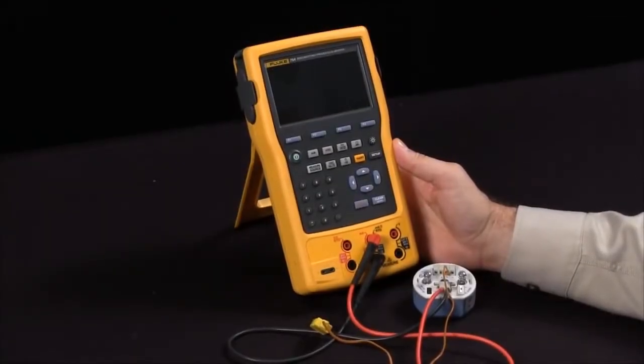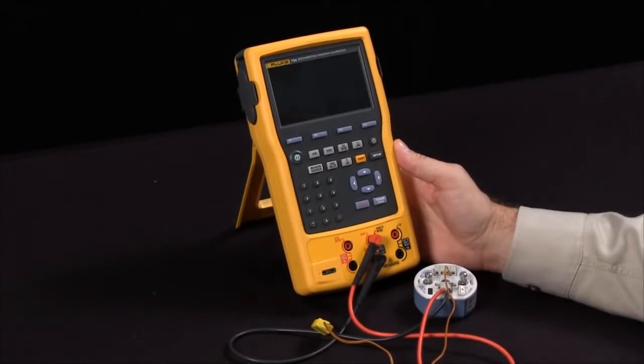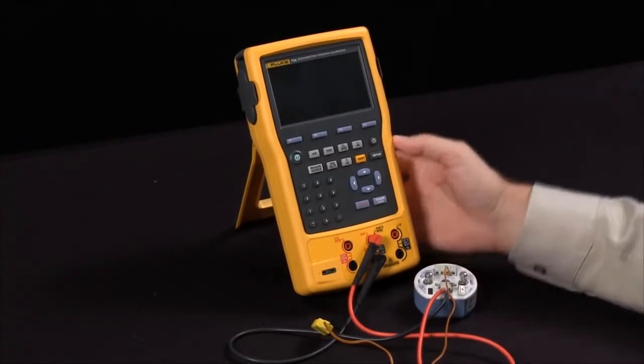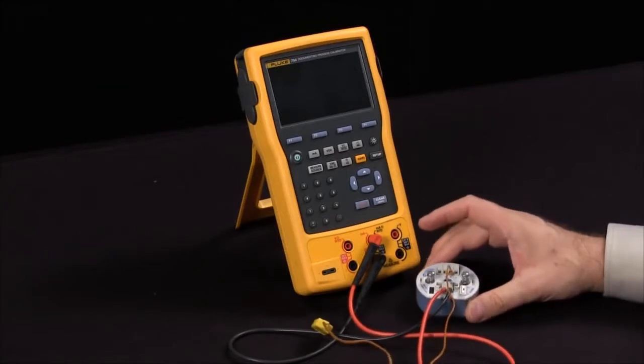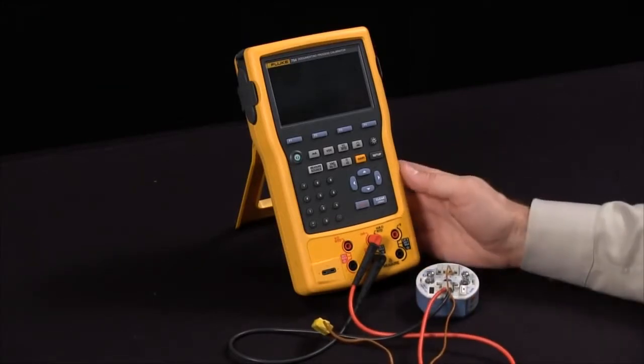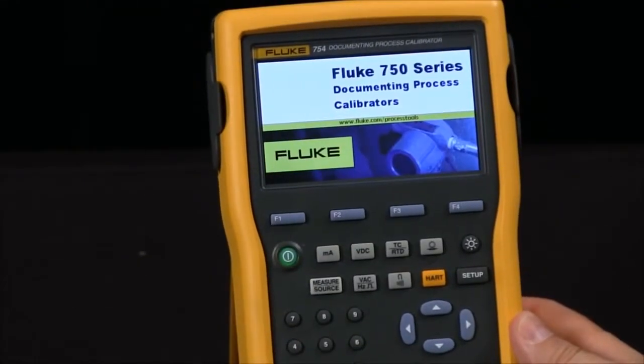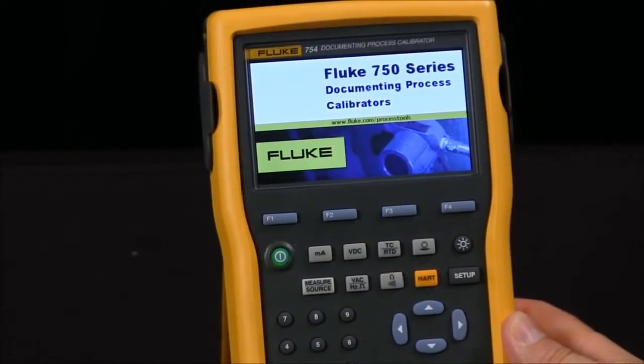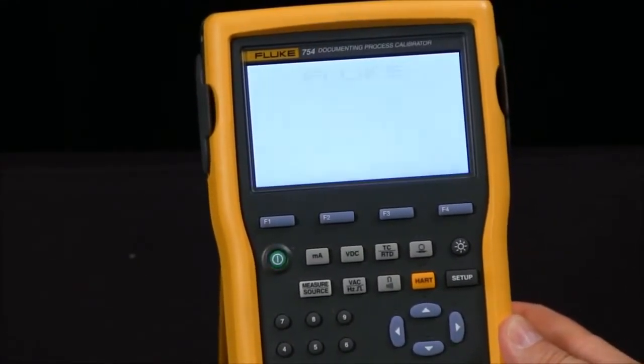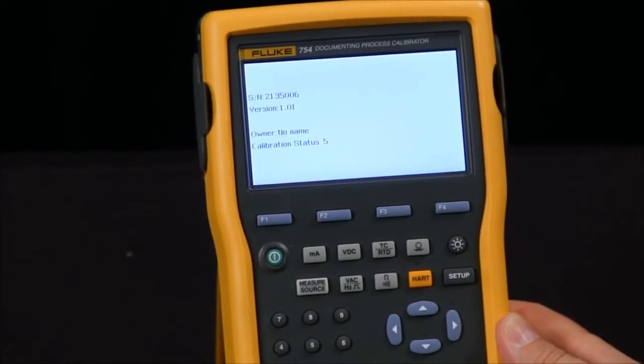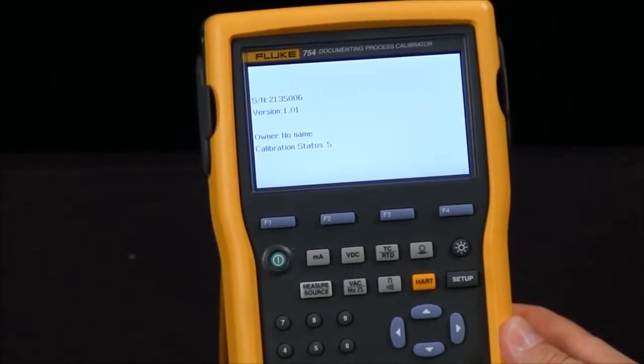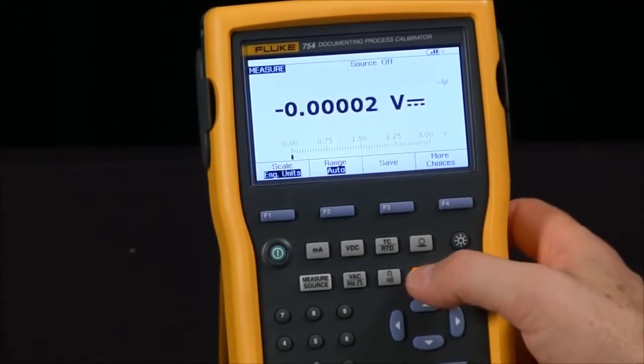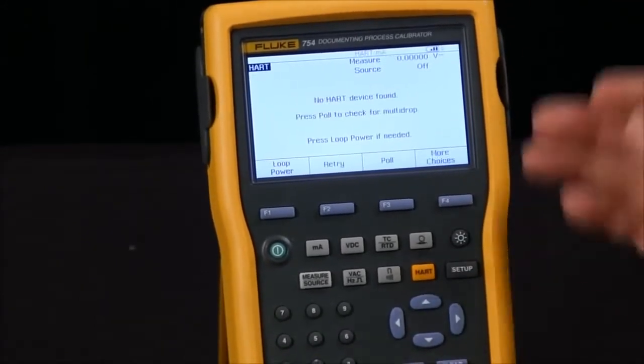Today I'm going to show you how to communicate via HART protocol and to perform a simple calibration with a 644 Rosemount temperature transmitter. I will power on the 754, and as soon as it goes through its initialization process, now I'm going to hit the HART communication device.